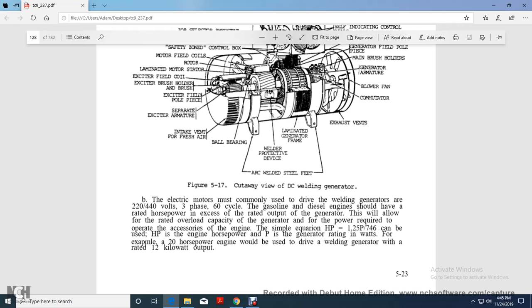the generator. This allows for the rated overload capacity of the generator and the power required to operate the accessories of the engine. A simple equation: horsepower is the power in watts times 1.25 over 745, or 746 can be used. Horsepower is used for the engine. The purpose is to match the power generated with the rating in watts. For example, a 20 horsepower engine would be able to drive a welding generator at 12 kilowatt output.